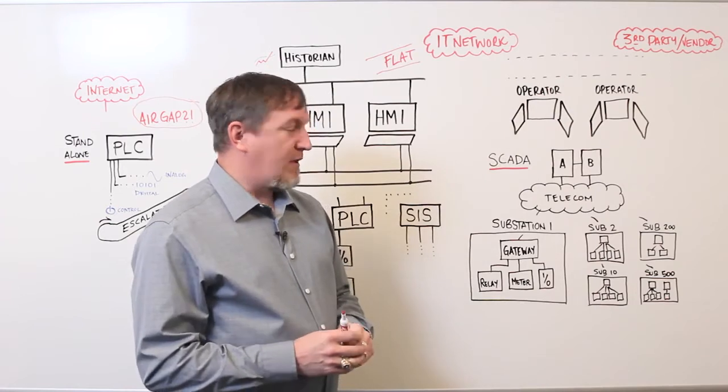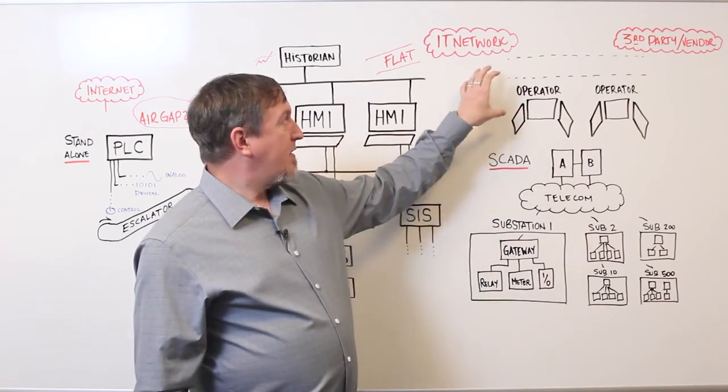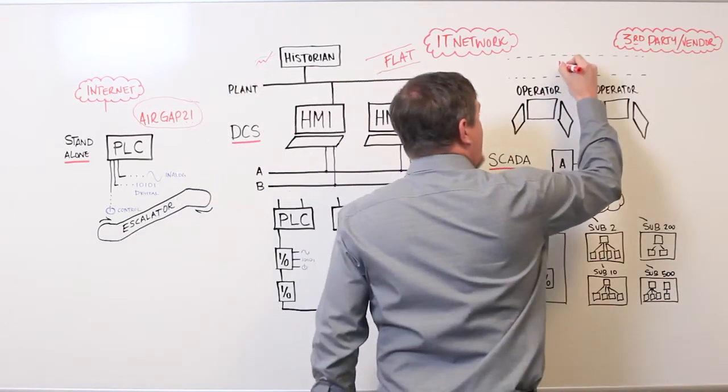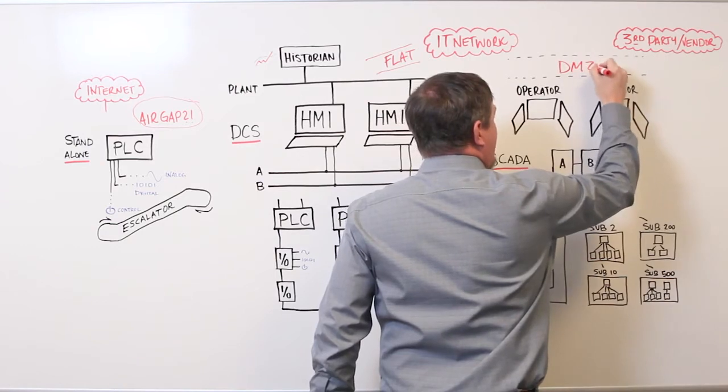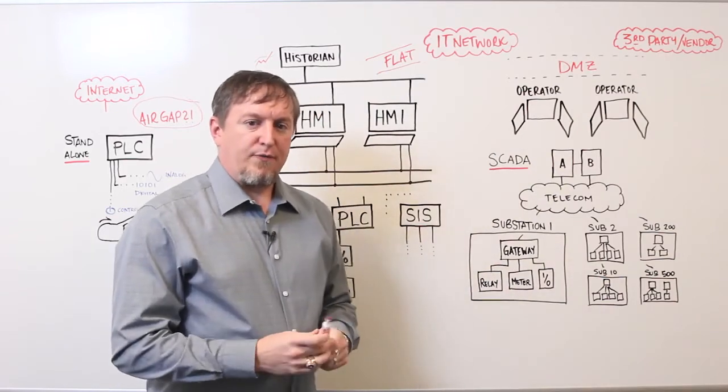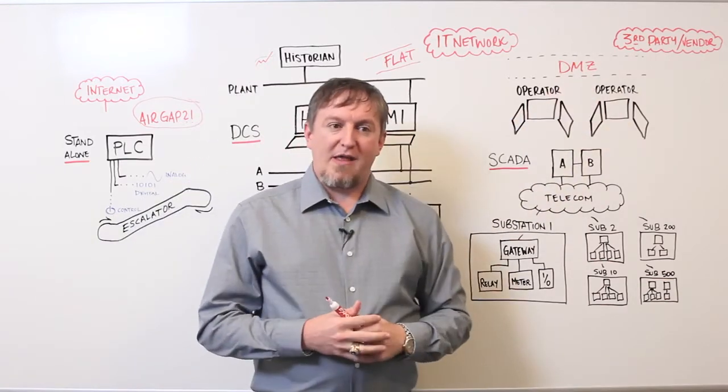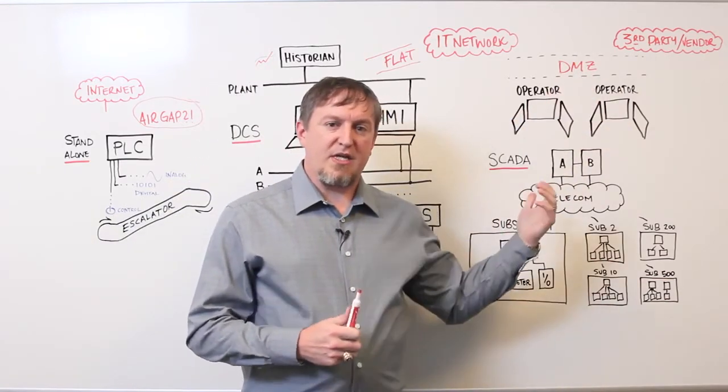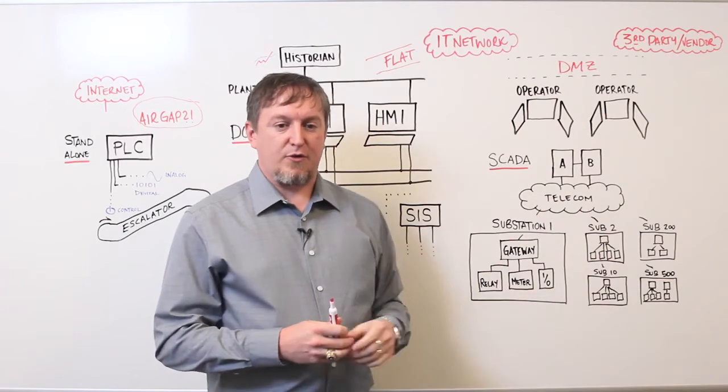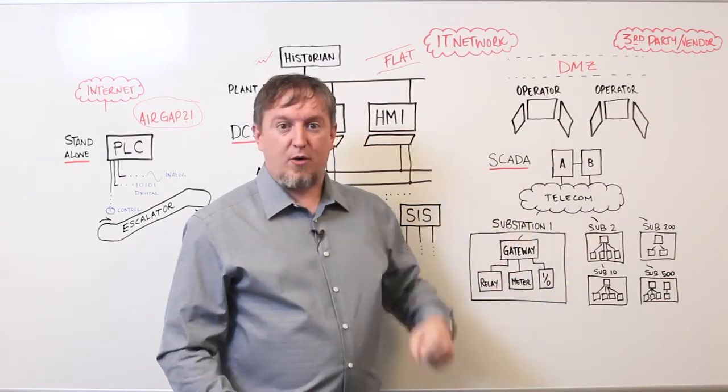We talked about another type of architecture reference model called the Purdue model. In between the IT network and the SCADA network, we have a DMZ, which stands for demilitarized zone. That is a safe area where, if someone wants to get data in or out of the control system, they have to go through the DMZ. Even if you have a third party or vendor having remote connectivity to your control system, they have to get it from the DMZ and not from the control system itself. So, there's no direct connection to the control system from the third party or the internet.